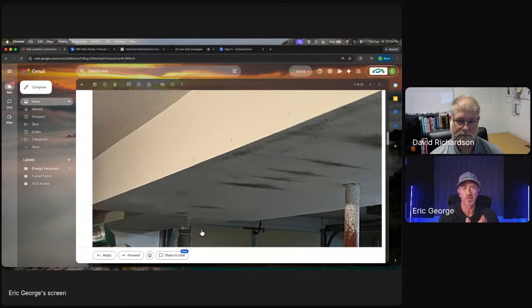And if it does need to be sealed, you want to do it the right way. Don't use duct tape — duct tape's not for ductwork. You want to use a UL 181 rated tape, or duct mastic is the best thing to do.